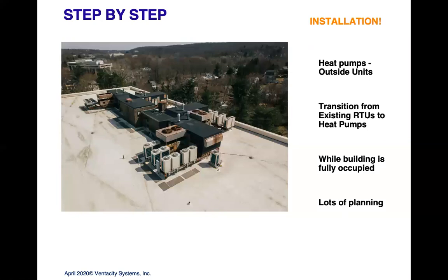And this is what it looks like on the roof. That was with half the heat pumps, so one side of the building done with heat pumps. Most of this big equipment here is all gone now. All this old stuff that was about 40 years old is gone. There are two 3,000 CFM ERVs here. And now this is all heat pumps down here, and most of this big equipment is gone. And there are two more 3,000 CFM ERVs. And that project is now fully up and running. And we're starting to collect data, full building data, and have results. A year from now, we'll have a good one year's worth of data. And we expect it's going to very much exceed the model that we had done.